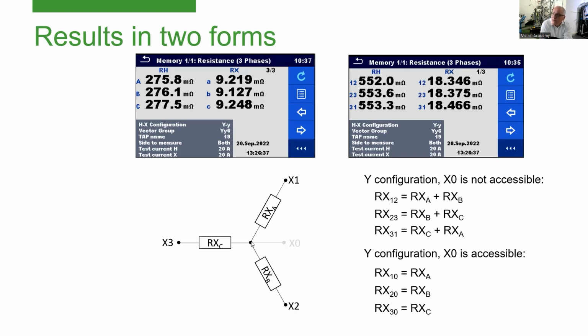In this simple case, for example, once again, if you look here, usually you connect the instrument to X1 and X2, and you measure the resistance between these two points. That means you measure the resistance of two windings, winding A and winding B. So in the winding resistance analyzer, you get on the first screen this value, which is the value between X terminals 1 and 2, and represents two windings. In the DTA, after all the measurements have been performed, you get calculated values from all these results. So in winding resistance, you get two screens.